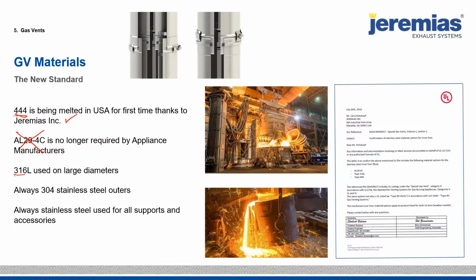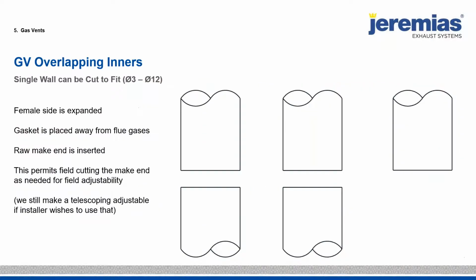Like the conical and the flange, we always use 304 stainless on the outer jacket because again, the systems are always maintenance free. That's important. And like always, the supports and the accessories are all stainless as well. Now what we do on the gas vent system, the small system, this is being sold through a lot of distributors. They like stocking the single wall systems because it's field cuttable just like plastic.